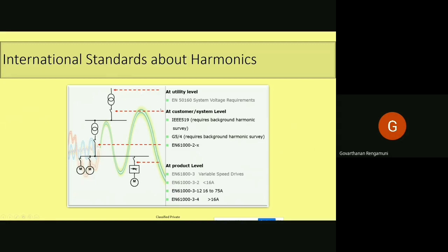Here you can see that at different levels, different standards describe the limits for harmonics. At the product level, there are different standards from IEC, defining the limits based on the current rating of the equipment. Similarly, at the utility level, EN 50160 gives the system voltage requirement, how much allowable limits there can be. The third one is at the customer and system level. For example, the point of common coupling is covered by IEEE 519 and G5/4. G5/4 is for the UK, and IEEE for international and the EN standard for Europe. So they are defining different limits at the PCC level.